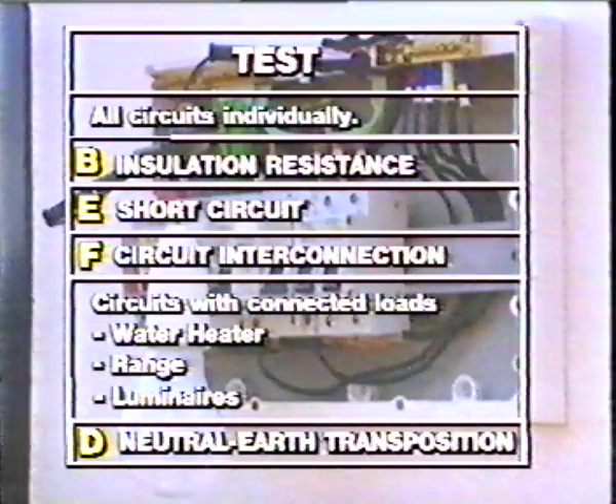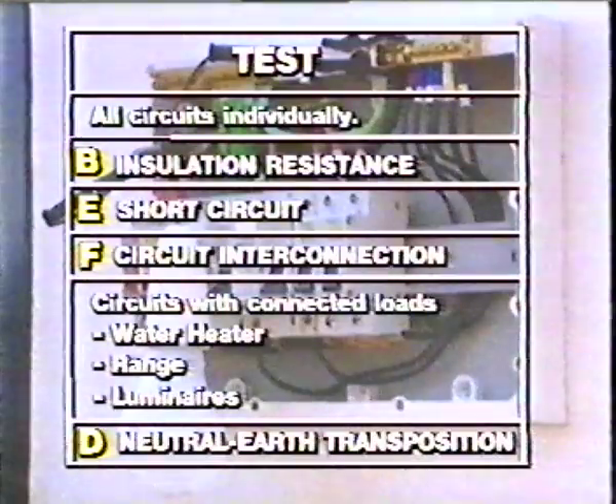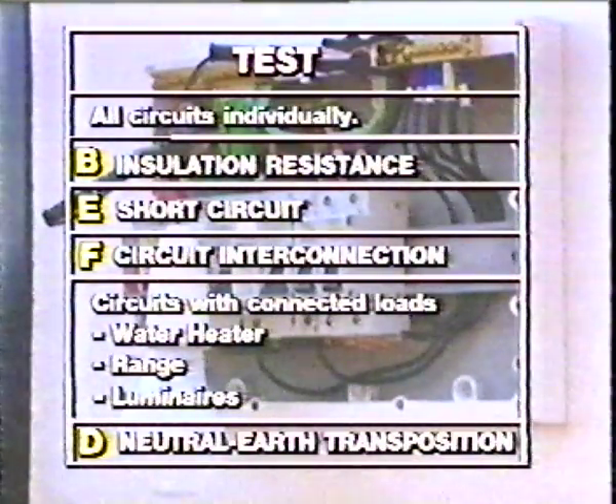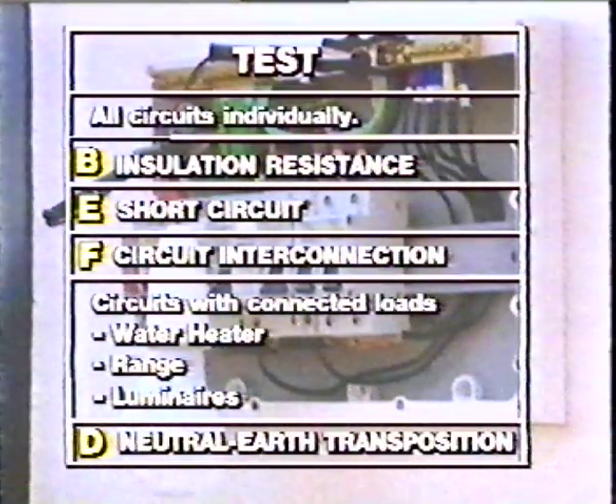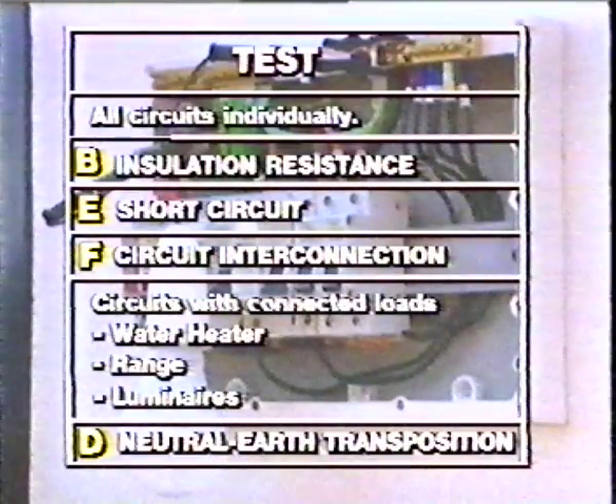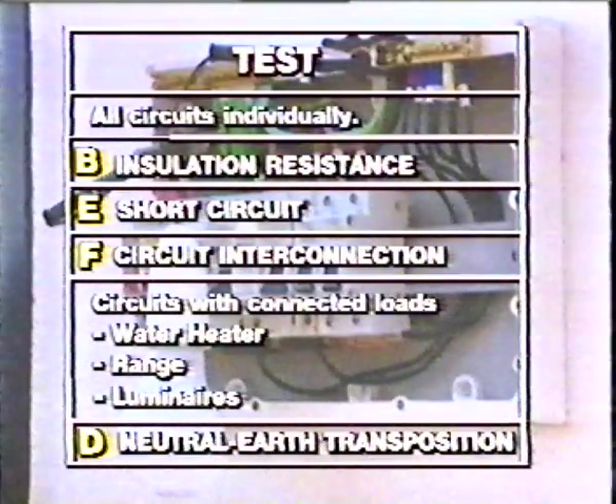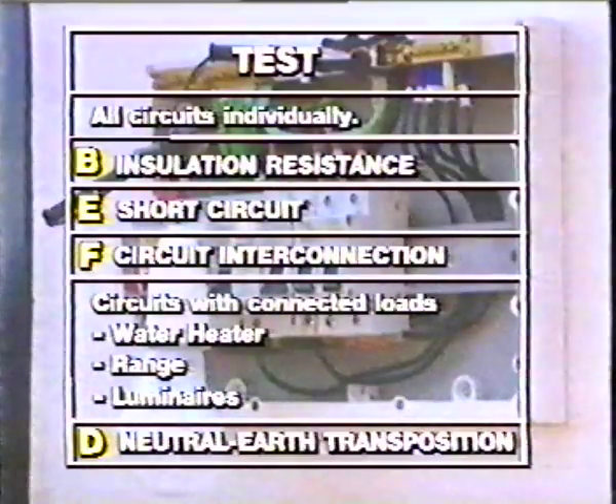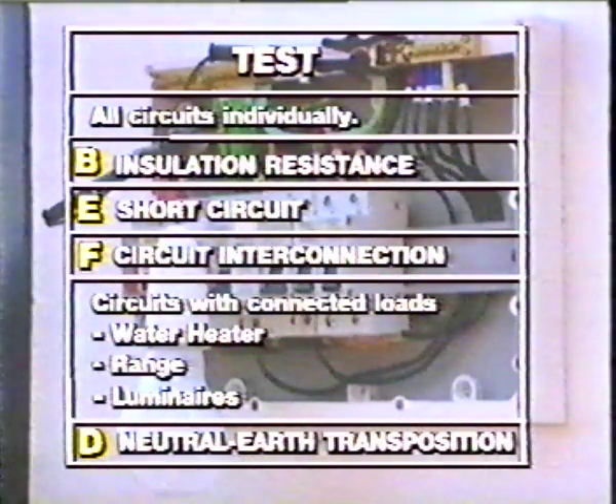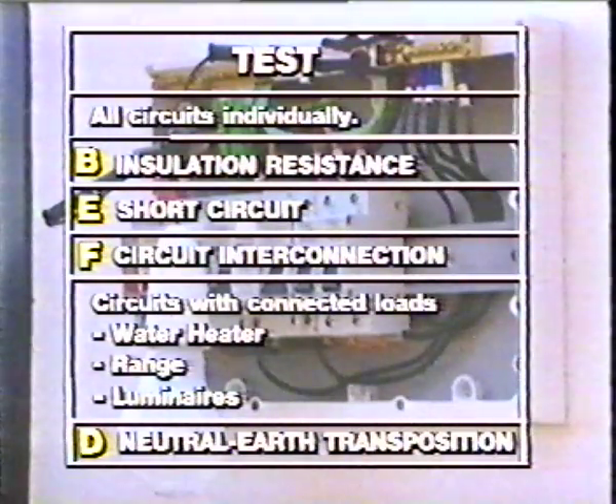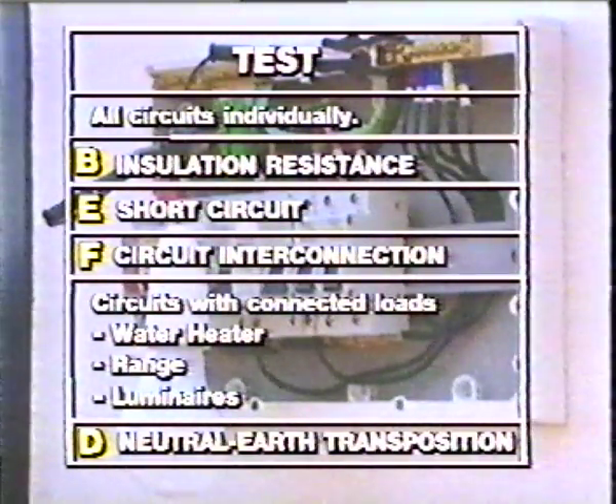To test for neutral earth transposition on socket outlets, the neutral conductor of the final sub-circuit being tested is disconnected from the neutral link, and a 60-watt lamp is connected between the conductor and the neutral link. With one lead of the ohm meter connected to a known earth, the other lead is connected in turn to the neutral and earth contacts at the outlet.